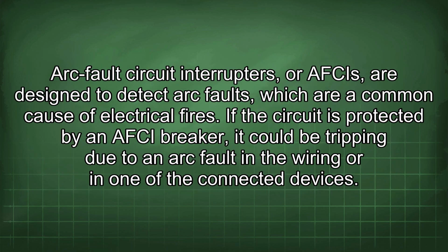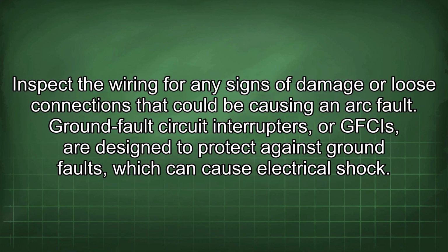Arc fault circuit interrupters, or AFCIs, are designed to detect arc faults, which are a common cause of electrical fires. If the circuit is protected by an AFCI breaker, it could be tripping due to an arc fault in the wiring or in one of the connected devices. Inspect the wiring for any signs of damage or loose connections that could be causing an arc fault.